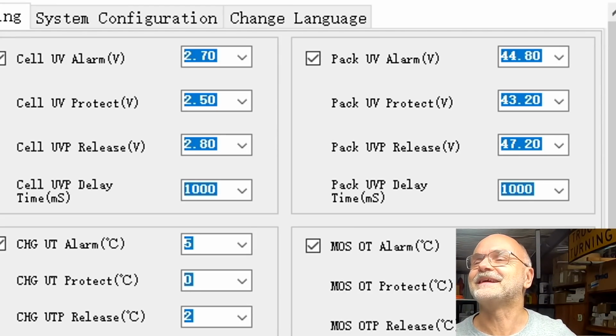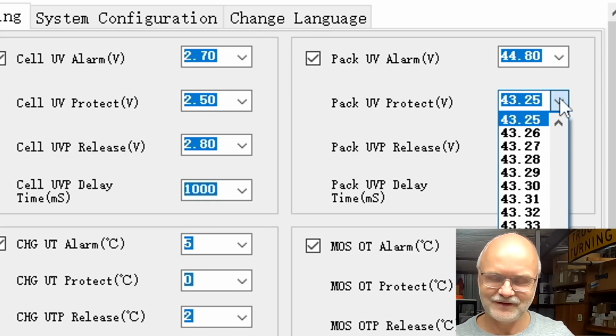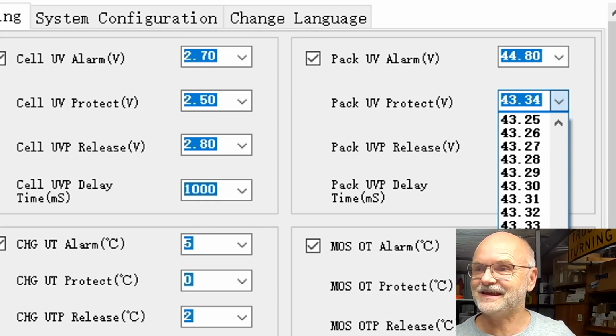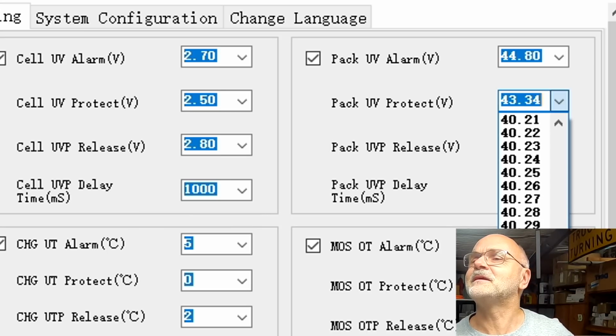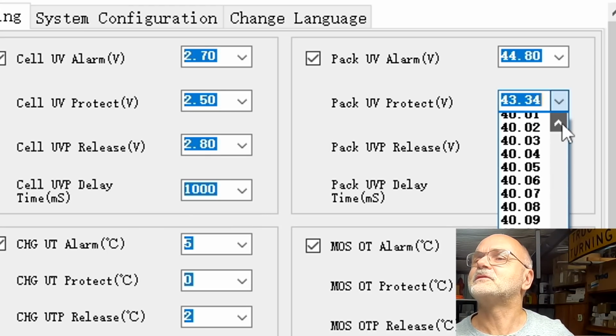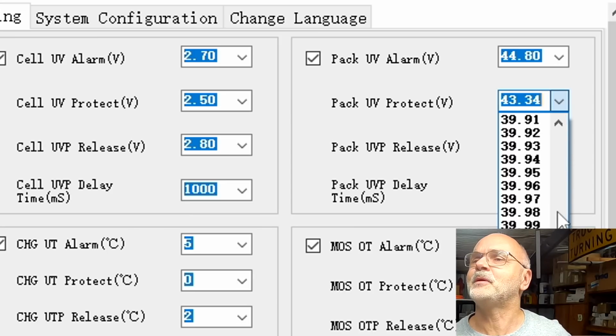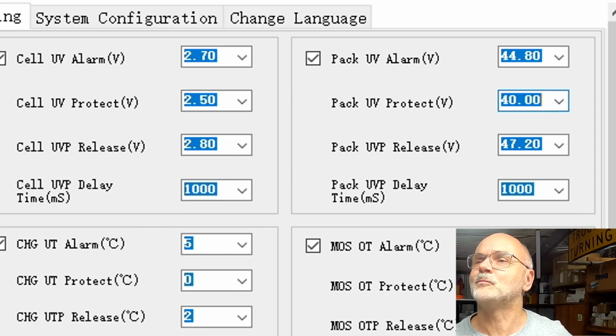Oh, my bad again - the pack under-voltage protection is sitting at 43.2 volts for some reason. I don't know what's going on here, this should be at 40 volts. Guys, I'm not going to repeat the test again. The battery is meeting its specifications, and you will definitely get over 100 ampere hours out of this battery pack, and more than 5.1 kilowatt hours.